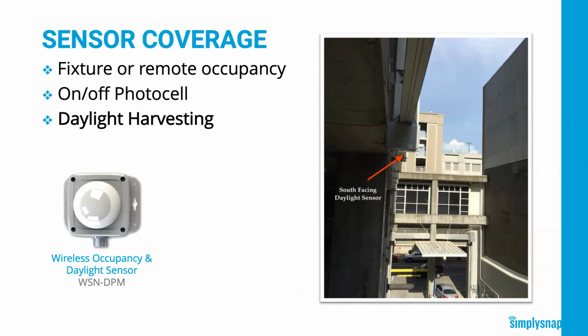Now for energy codes like Title 24, on-off control is not enough. In parking garages where there's a combination motion and daylight sensor in every light, one of the biggest issues we've seen is that you can't get a reliable reading from the surface of the garage. The garage is dirty, and there are cars moving through the structures, which can even cause the sensors to falsely detect light. So what we recommend is using a sensor pointed out at the natural light, as you can see in this picture, versus down at the surface. That one sensor can cover control for a whole group of lights on that side of the garage, which is very important for Title 24.